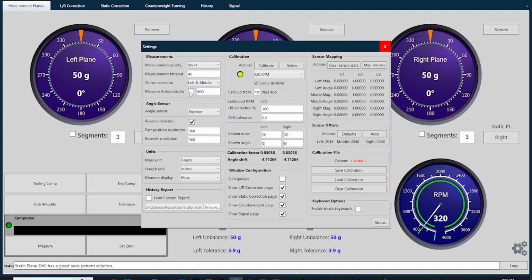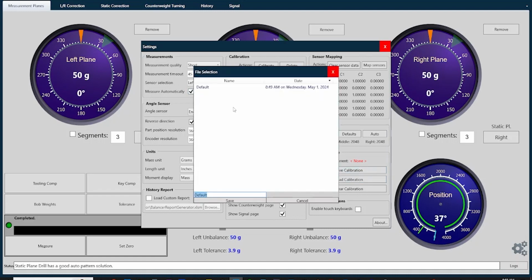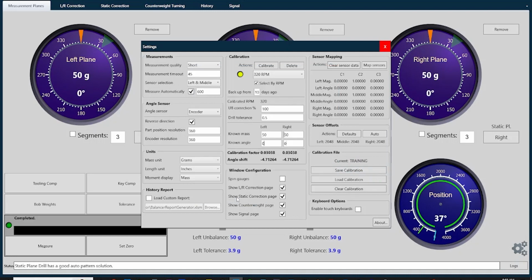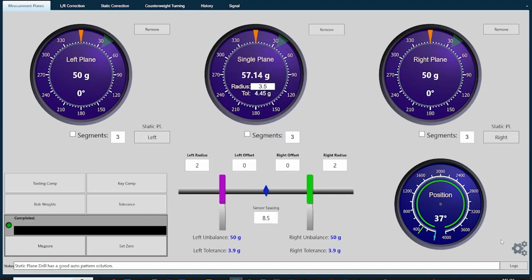In the left column, there is another checkbox next to Measure Automatically. Set the value to your most common balancing speed and check that box so it will auto-sample when you're close to that speed. This number can be adjusted at any time, but it's recommended that it be left on your primary balancing speed. After completing all these steps, you can press Save Calibration located in the lower right-hand corner of the settings window. Then, hit Save at the bottom of the box that pops up. This ensures that your machine is now calibrated and ready for the balancing process.